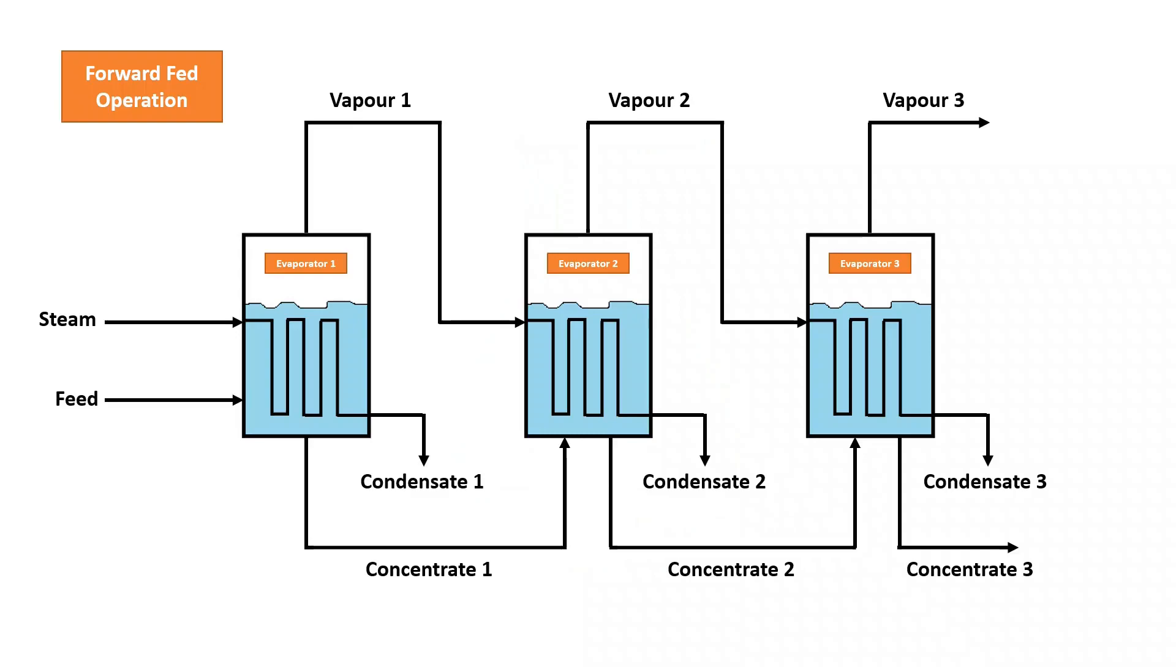In a standard single effect evaporator, the vapors produced would normally be discarded. However, in a multiple effect evaporator, the hot vapors from the first effect are passed to the steam chest of the next effect in line, which in this case is evaporator 2.